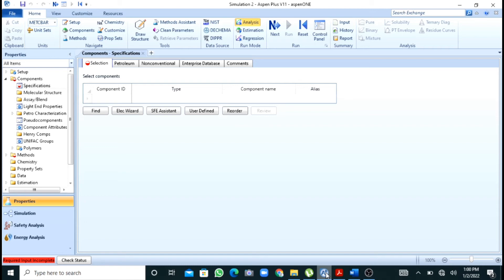In rigorous design, the overall heat transfer coefficient is calculated by taking into consideration film coefficients as well as thermal conductivities. Rigorous design includes design, rating, and geometry of the heat exchanger according to TEMA classification. In the shortcut method, it only calculates the enthalpy balance, or energy balance, and the overall heat transfer area requirement.